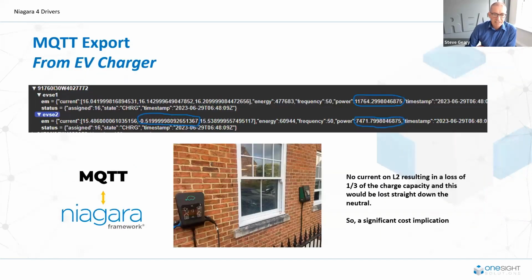Okay, I want to give you a bit of a use case that came up over recent weeks, and this is around EV charging. These are the chargers that we've got externally to our office, and I've recently taken delivery of an electric car. The car had a specification that it should be able to accept 11 kilowatts, and on the first day of bringing it to work to charge it, I sat down on the app with my technical director, who had his car plugged in on the charger next door. He was showing me on his app that he was pulling 11 kilowatts. However, from my car, I was only managing to pull 7 kilowatts. So we thought, what must the problem be? First we changed the leads and thought maybe I've got a problem with my lead. Tom used my cable, I used his. And actually I'm still only pulling 7 kilowatts, Tom's pulling 11.